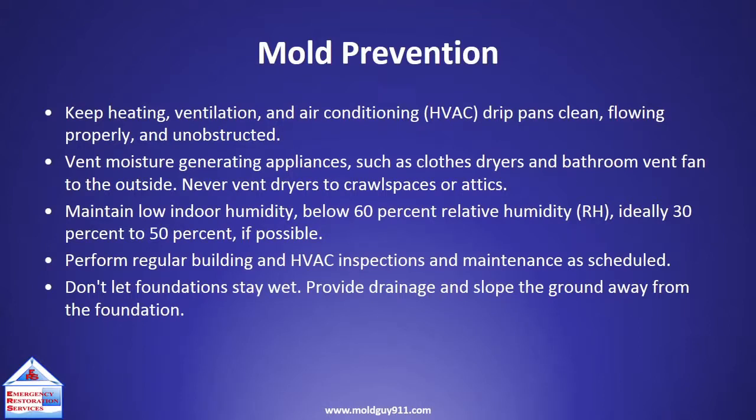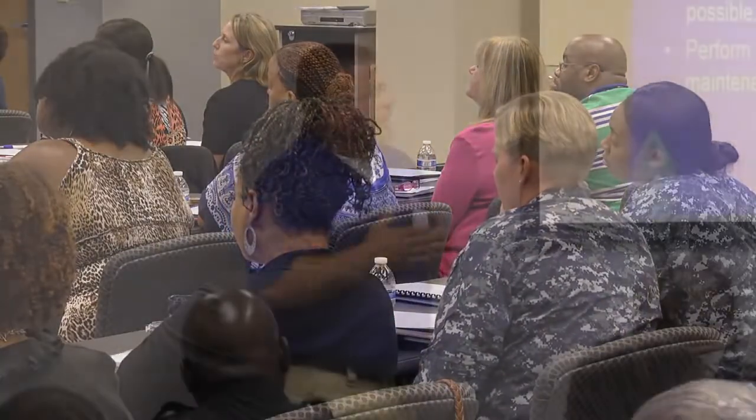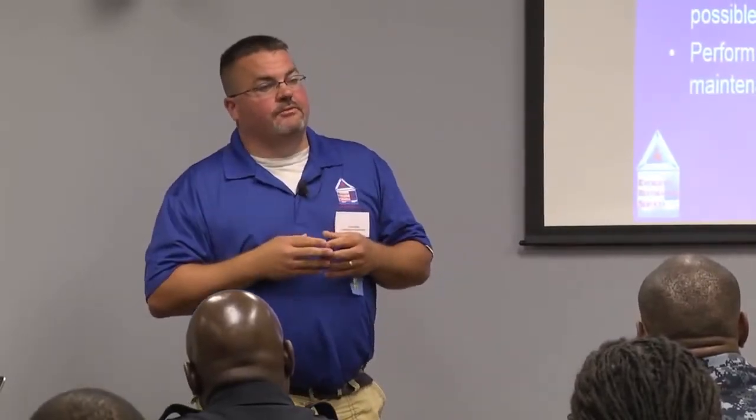We see this quite often, especially a lot of times in rental properties where you have an owner that doesn't want to make a necessary repair the right way. And so a clothes dryer vent or a bathroom vent fan will be vented into a crawl space or an attic space. Same thing, you're pumping hot, moist air into an unconditioned space, and it's going to cause a condensation issue and cause mold growth. Like I said, ideally 30 to 50% relative humidity is ideal. Over 55, 60 is when we start becoming conducive to mold growth.